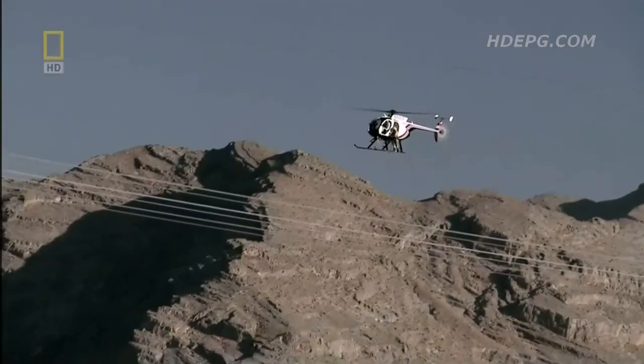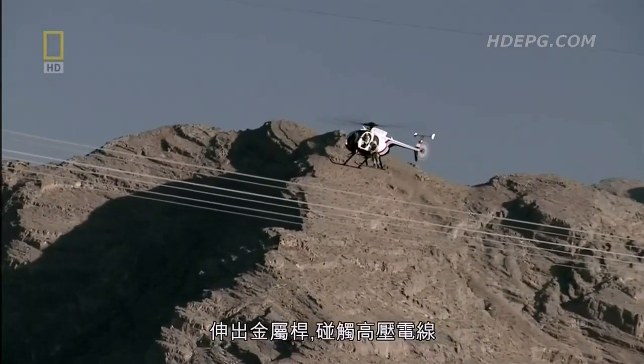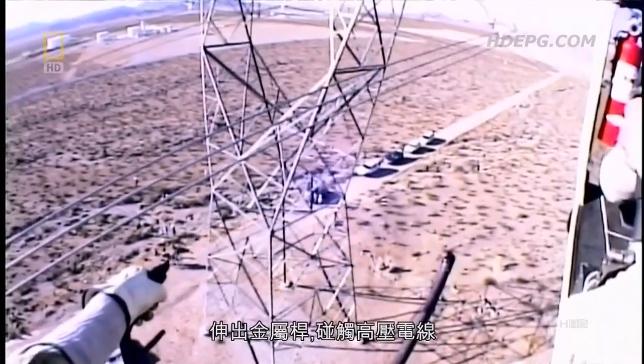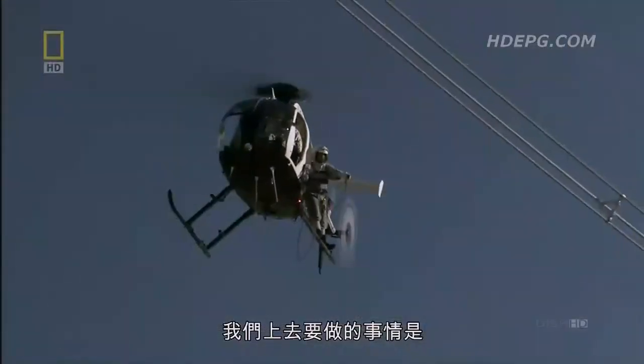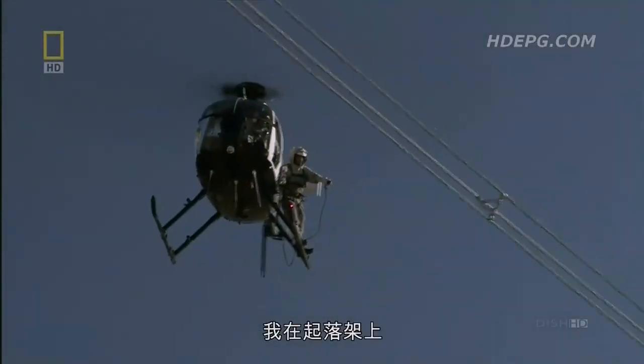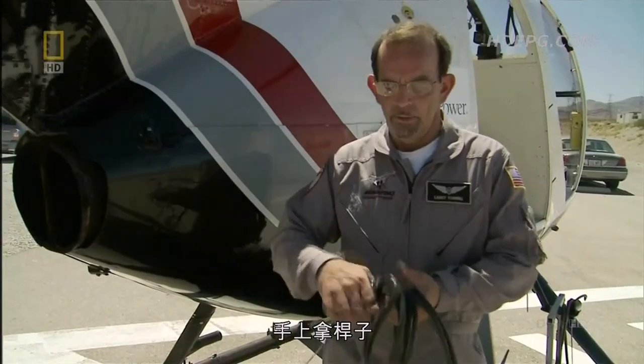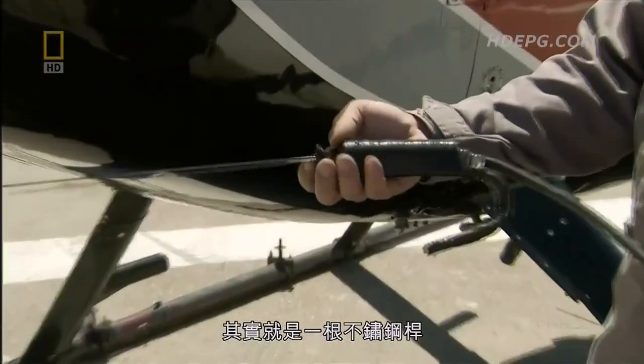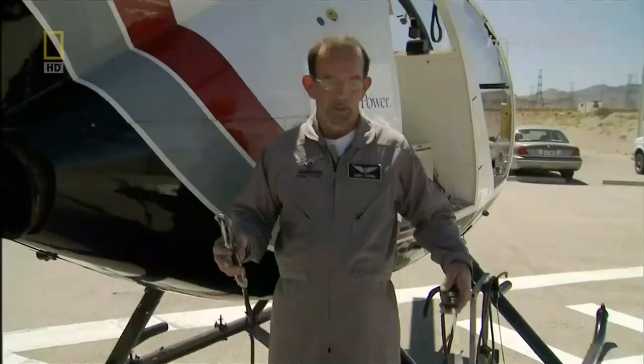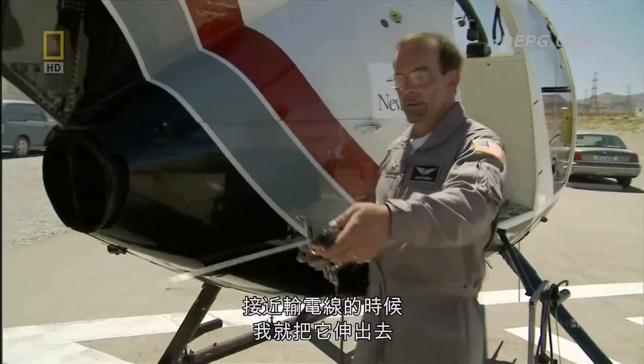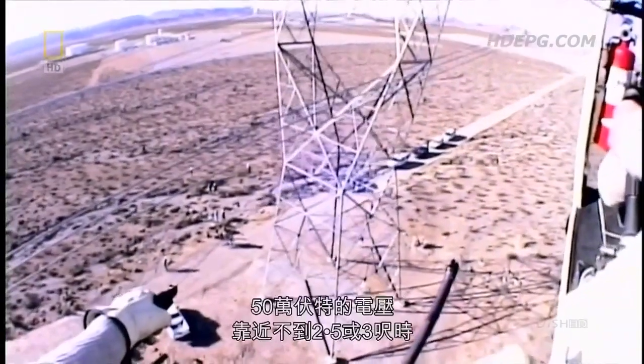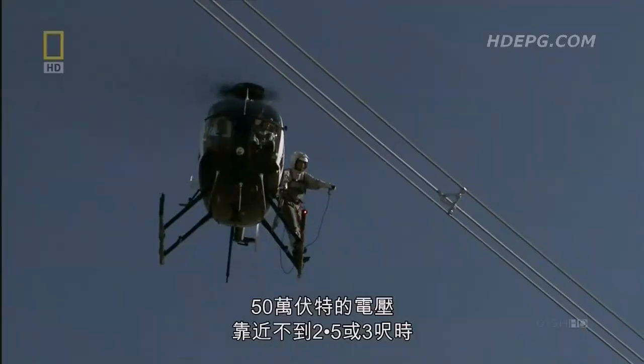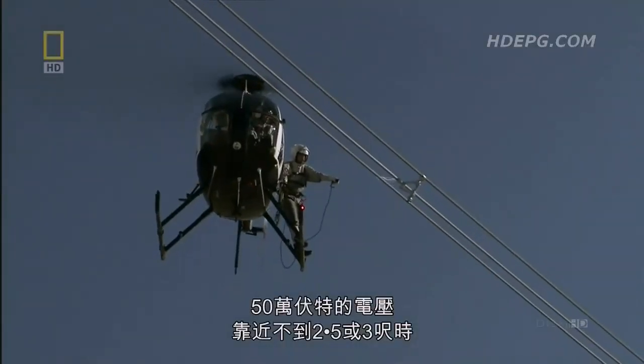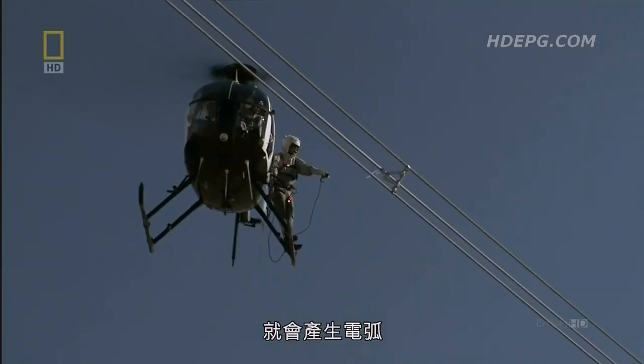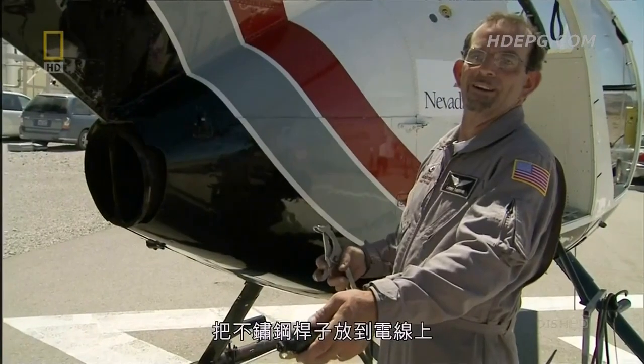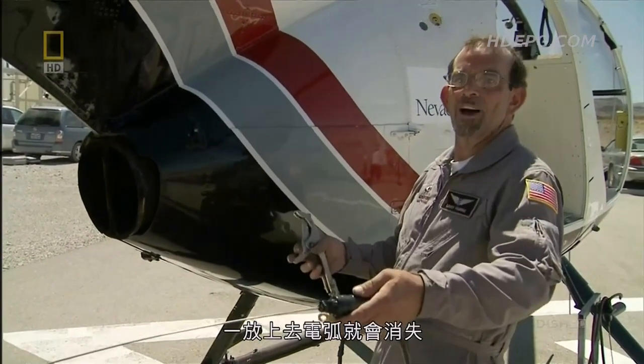His first step: reach out and touch the live wire with a bare metal rod. When we come up, I'm on the skid with the wand, which is nothing more than a stainless steel rod. When he comes in on that conductor, I'll have it out. With 500 kV, when you get within about 2.5 to 3 feet of it, it's going to draw an arc. You lay that wand on the wire, and once it's on there, your arc stops.